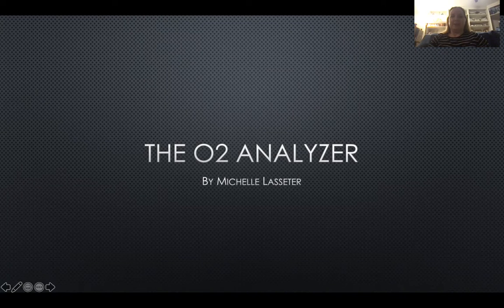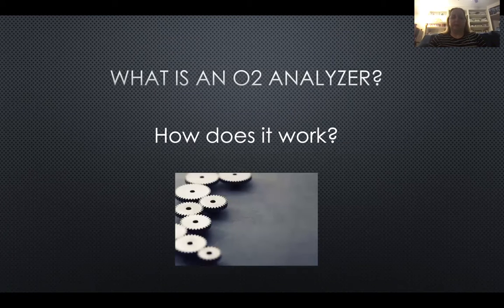Hi, my name is Michelle, and I'm here to tell you about the O2 analyzer, also known as a sensor. So what is an O2 analyzer? The O2 analyzer is basically a medical device that is used in various equipment, usually respiratory, and it measures the percent of O2 that is delivered.